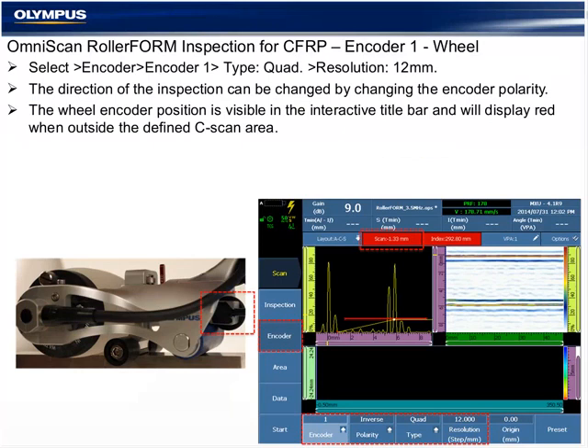Selecting Scan Encoder allows us to configure the resolution and type for the wheel. This is a standard Olympus quadrature encoder. It has a resolution of 12 millimeters that is written on the encoder. You can also calibrate the encoder if that's part of your procedure, or if something has changed that would have affected the resolution, under the wizards for calibration and encoder. We can inverse the polarity and change the direction for scanning forward or backward.